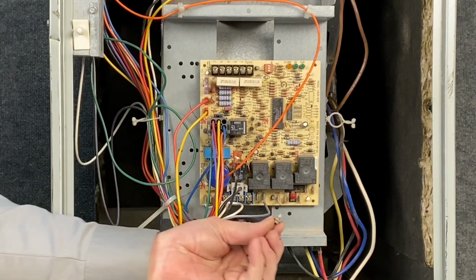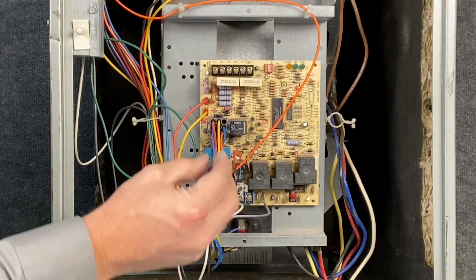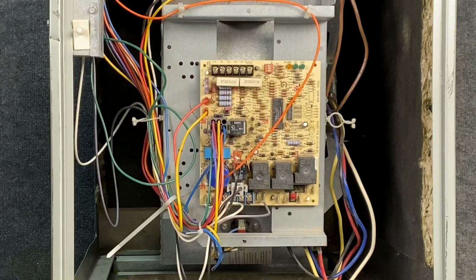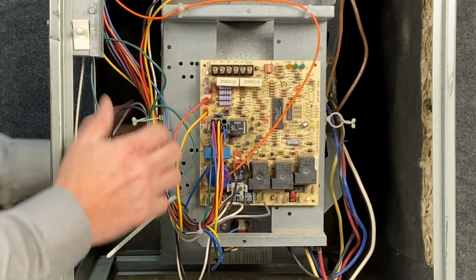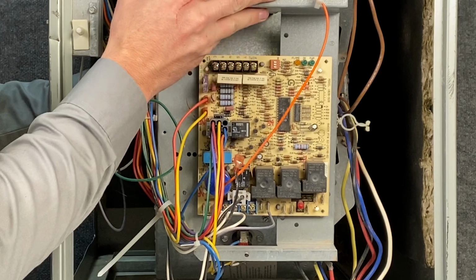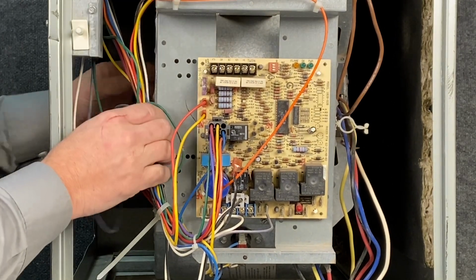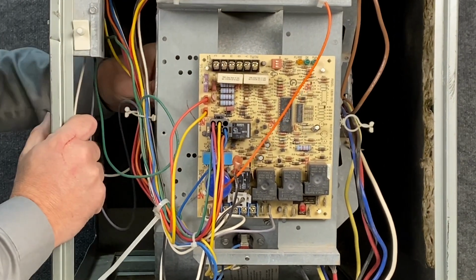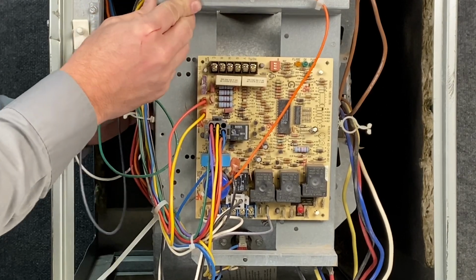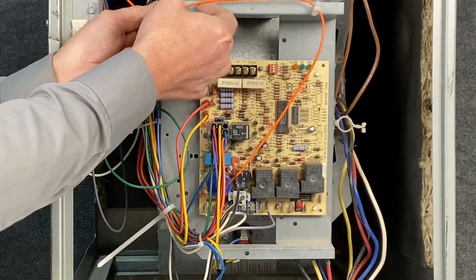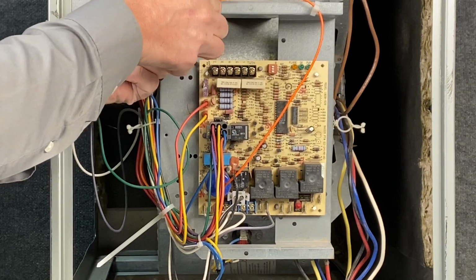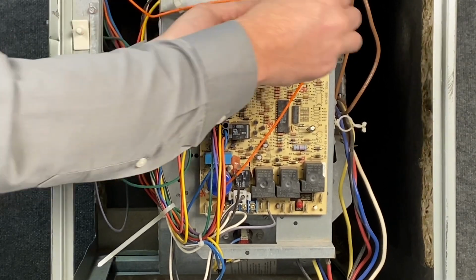These particular screws are very short, so I want to make sure I use these same screws when I put that blower back in. So now I'm going to slide this blower housing out, and now I can get to the rest of the screws much easier. If I'm pulling this out, I see that it's getting very tight right here. What I'm going to do is I can just loosen this connection here, and I want to make sure I put these wires back where they go, nice and clean.